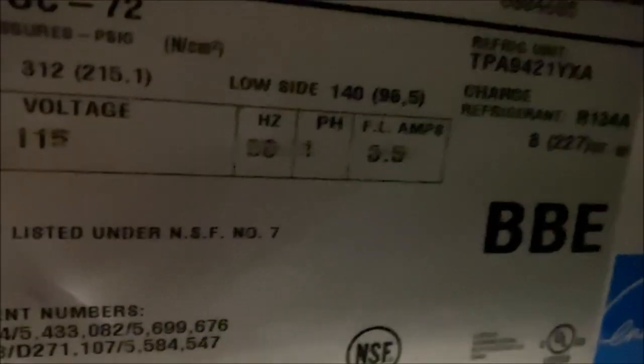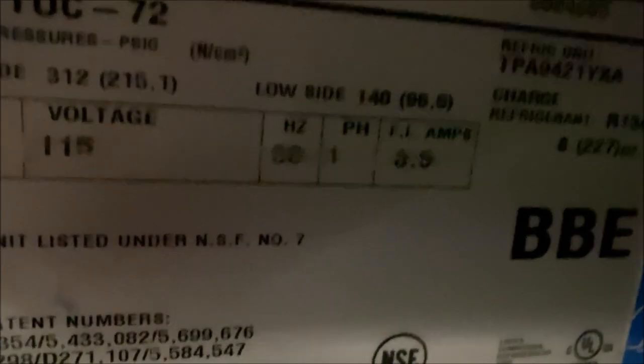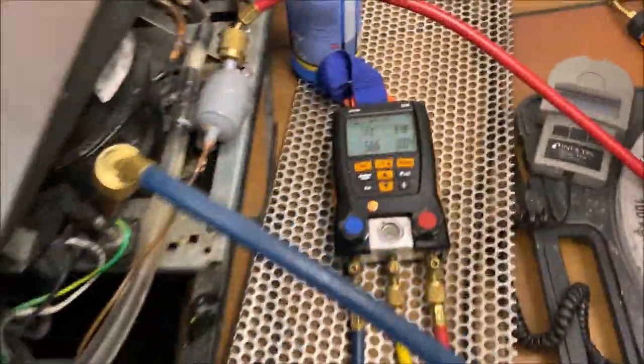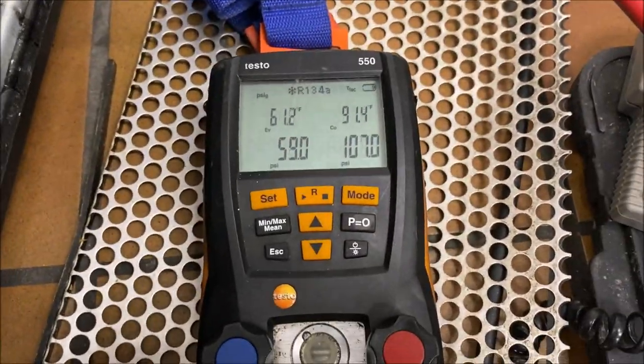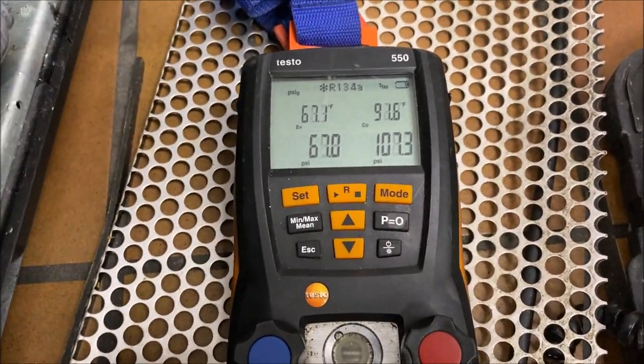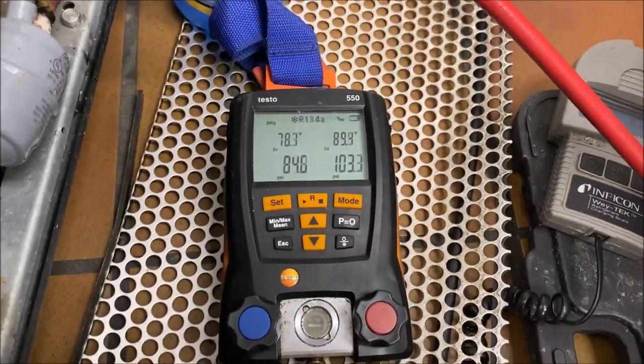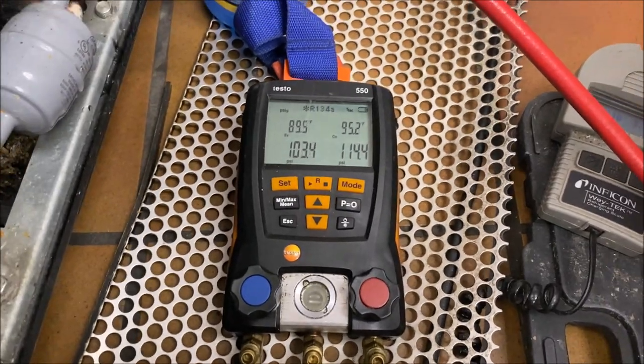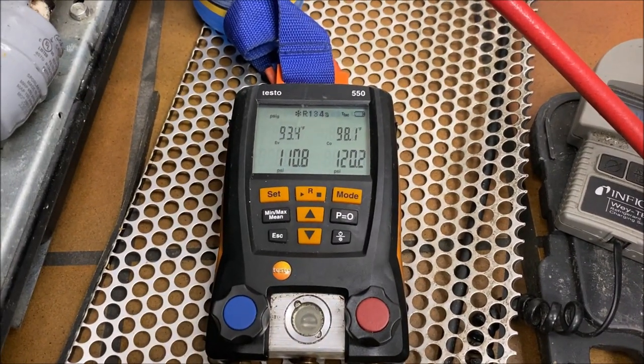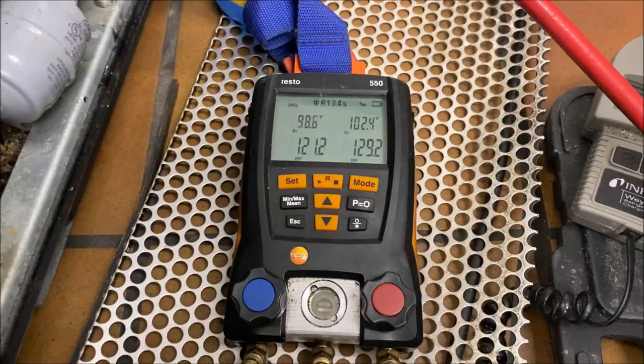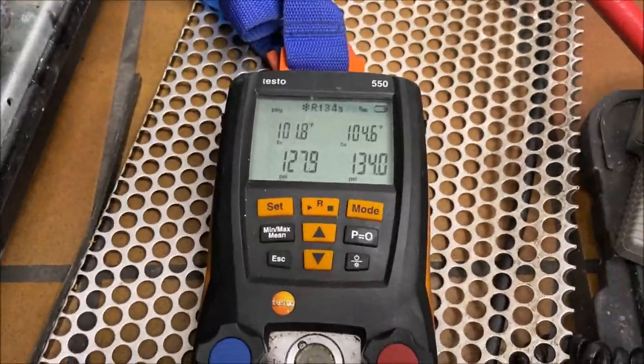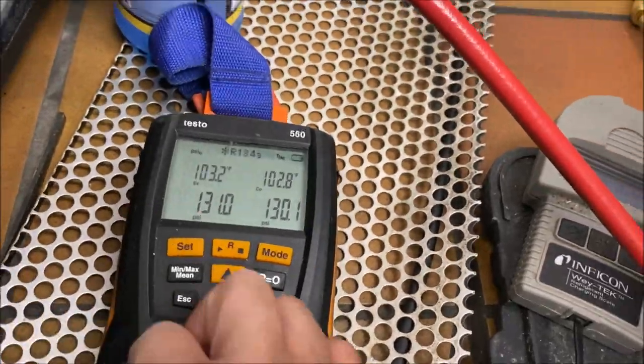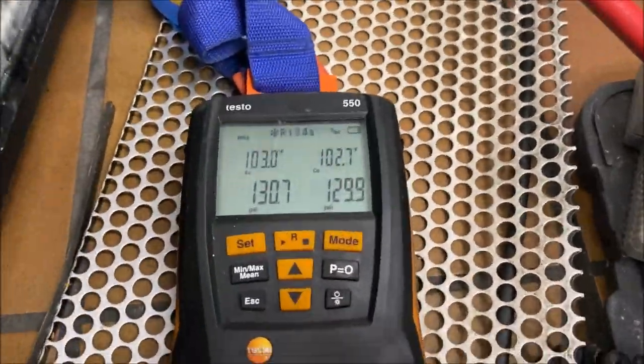So I'm going to put in nitrogen now. So you can see our low side can go up to 140 PSI, high side 312. So we're going to use that 140 as what we're going to test, or as close to 140 as possible. So let's go ahead and throw in some nitrogen and then let's get it up around 130-ish if I can, and let's go do another sweep test, and then hopefully this time we can find the leak. Like I said, it was only down 2.5 ounces, so the leak is pretty small. That's why I like to add in the refrigerant, not only to rule out that restriction in the system, but it tells me how big this leak is going to be.